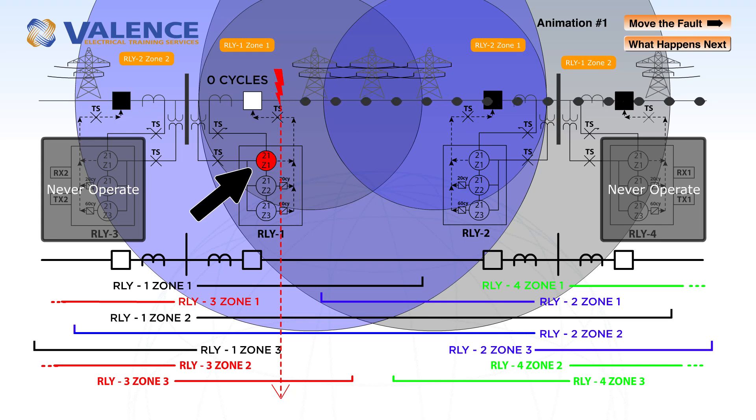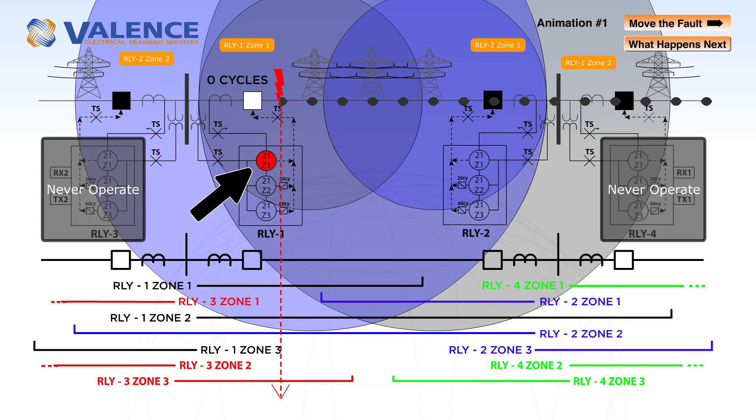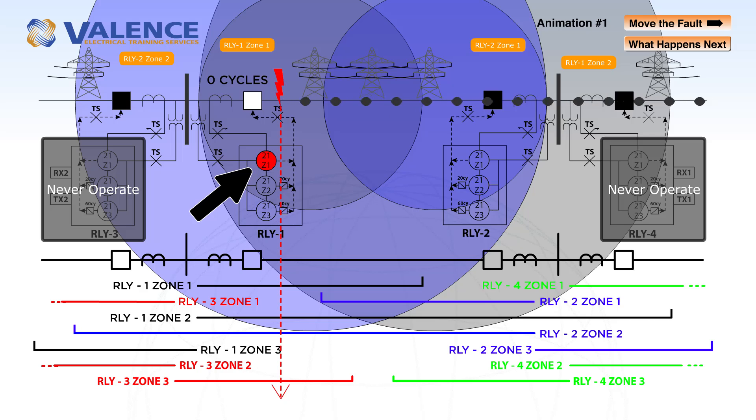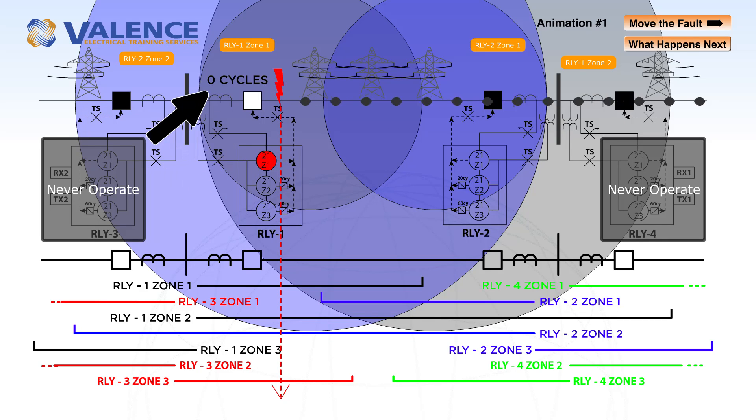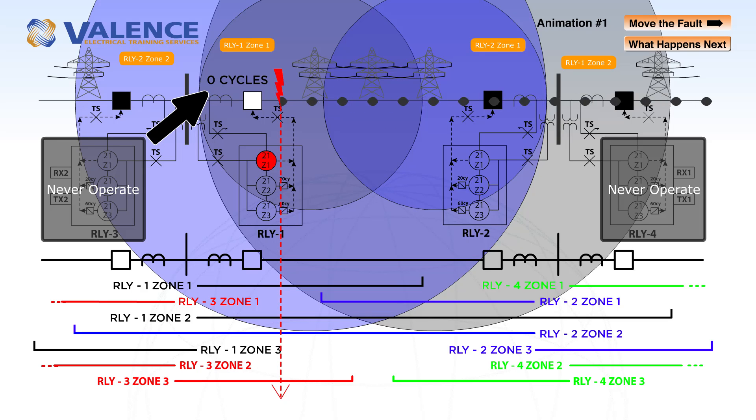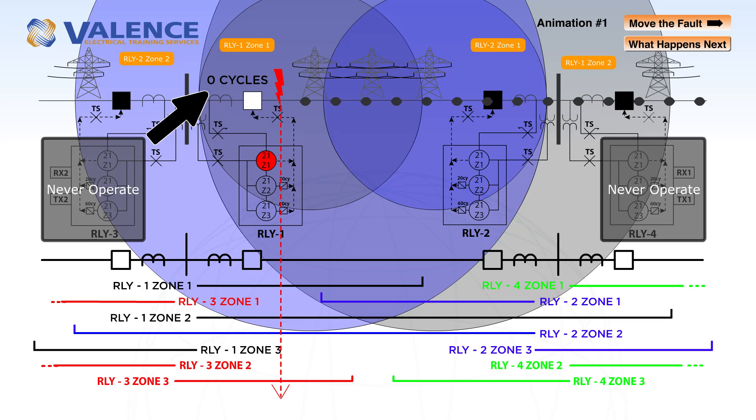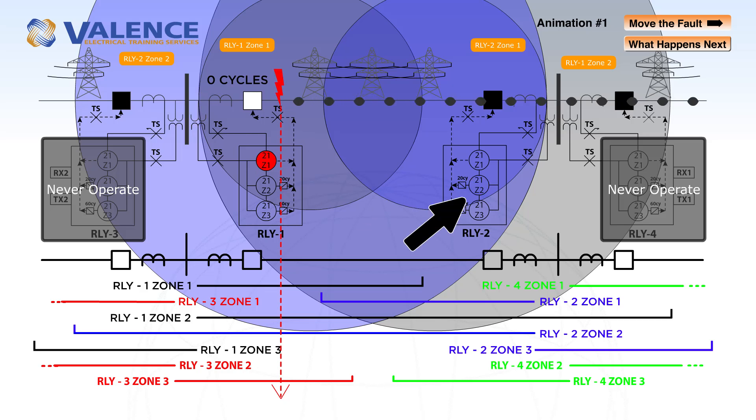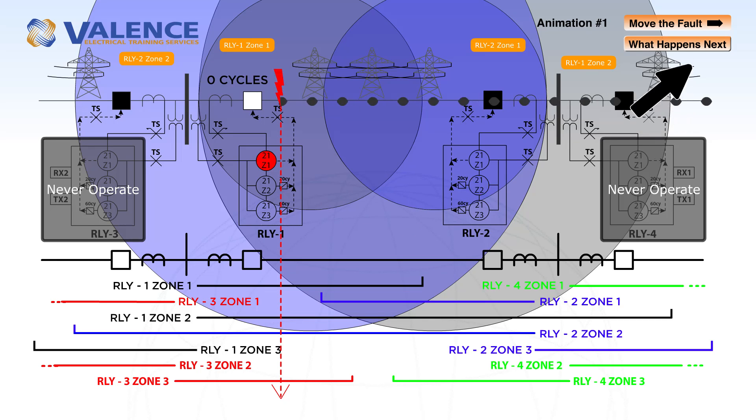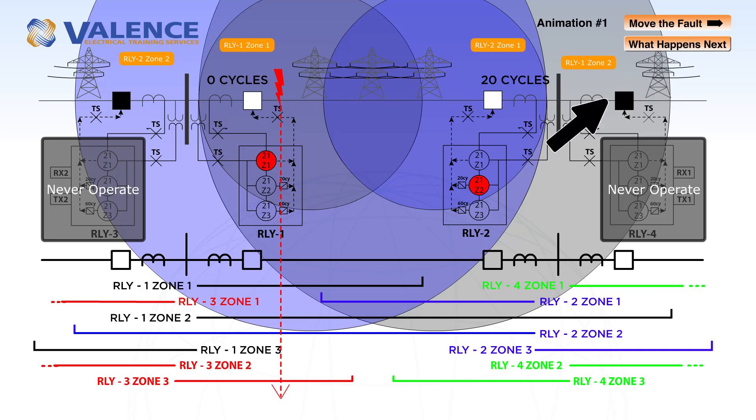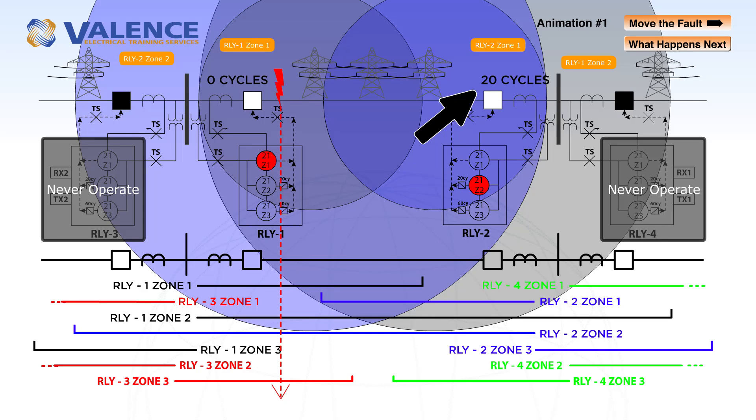Relay 1 is going to operate first because there's no intentional time delay set for zone 1 and relay 1 detects a zone 1 pick up. The description above the breaker indicates 0 cycles here, but it's really somewhere between 0 and 3 cycles. Zone 2 still has a source on the other side feeding the fault, and so relay 2 zone 2 will trip about 20 cycles later.